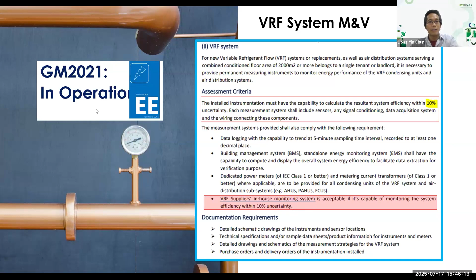Even if a VRF supplier has an in-house monitoring system, like Daikin or Mitsubishi with their own COP reporting, that system still needs to be certified or verified to within plus or minus 10% uncertainty. So this is the problem statement from Green Mark 2021.